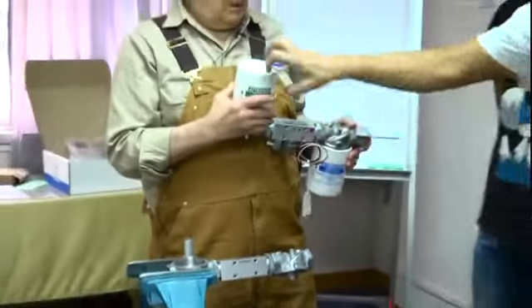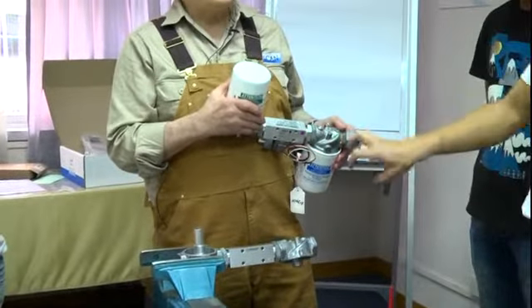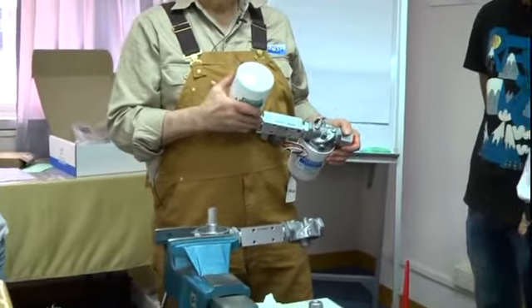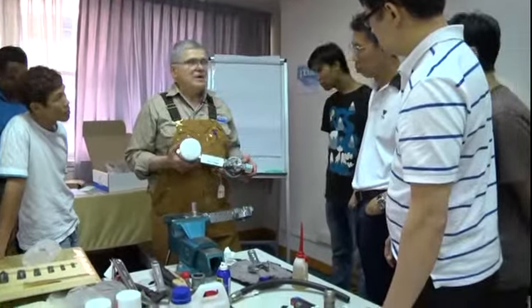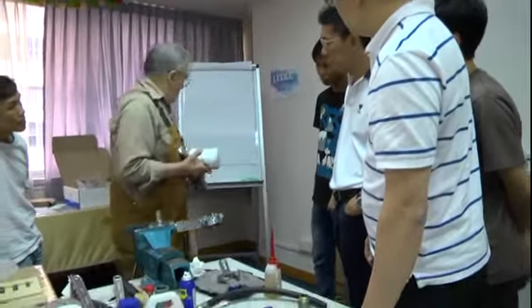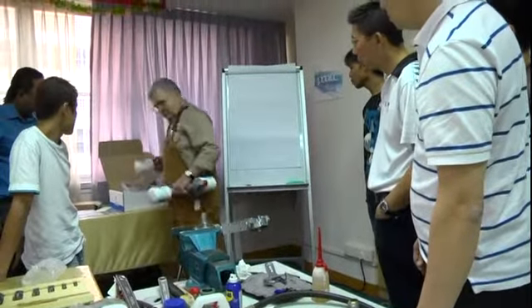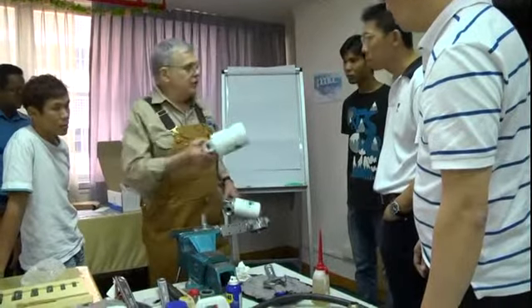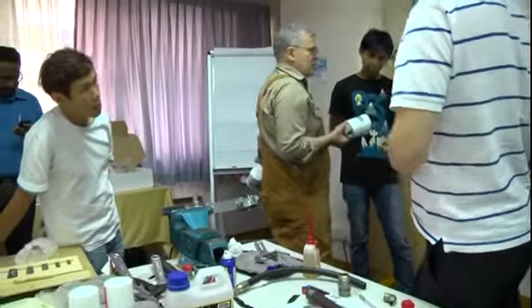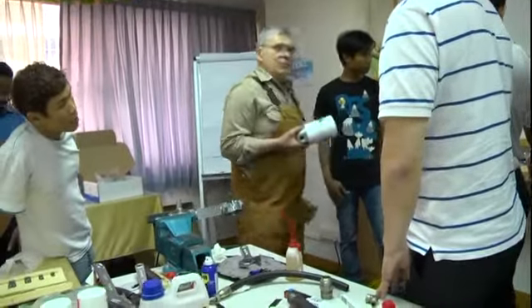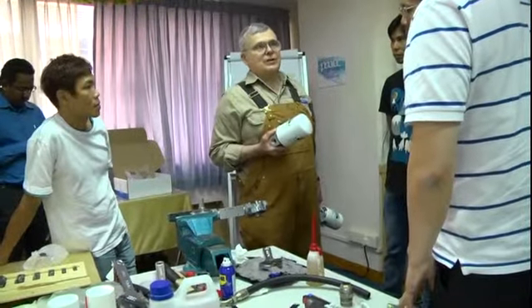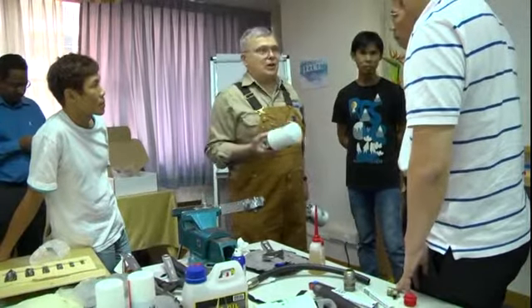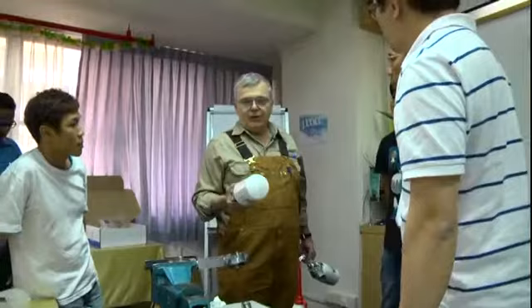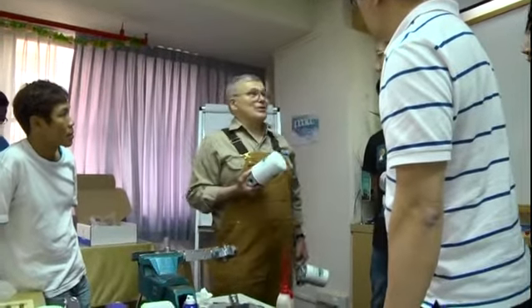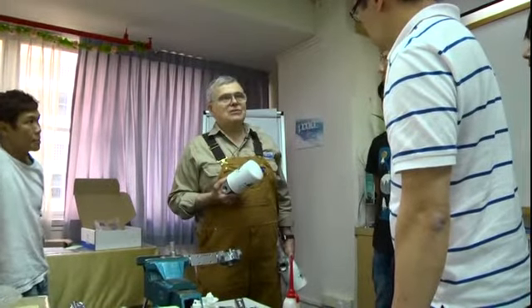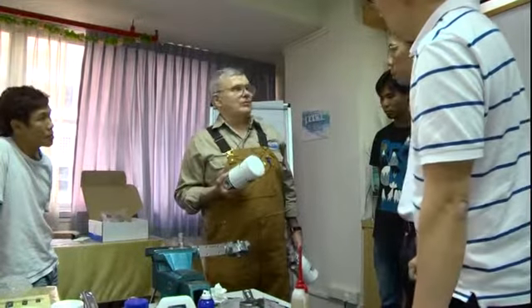Isn't this canister the same, or are they different in structure inside? It's the same structure. Our canisters are exactly the same. We identify them like this so the customer knows what they are. But if you had to replace a canister and it has a different color label, like this one on the return side, that one says it's a combination flow homogenizer and pulsation damper, but all these canisters have the same components inside. So if the customer damages a can and you have a can available that's not the right one, don't worry about it, put it on. You can take the stickers off and put the right stickers on. They're exactly the same. You don't have to get an emergency shipment from us.